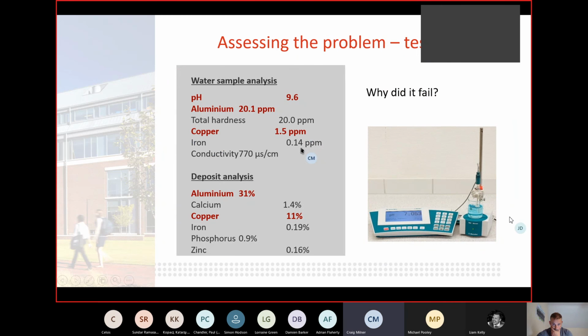What we found is that the pH was up at 9.6, with over 20 ppm of aluminium. Just to put that into context, you shouldn't have more than 1 ppm of aluminium, and it shouldn't be more than 1 ppm of copper, and that's why that's in red. So the copper was just over, and the aluminium was 20 times where it should have been. Iron, very little iron corrosion. If you're using X100, we can look after iron levels up to 125 ppm, as long as the Sentinel X100 is dosed correctly. Something had been added to the system, as you can see by the conductivity that was raised.